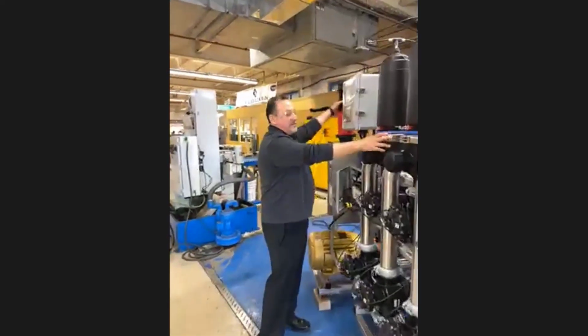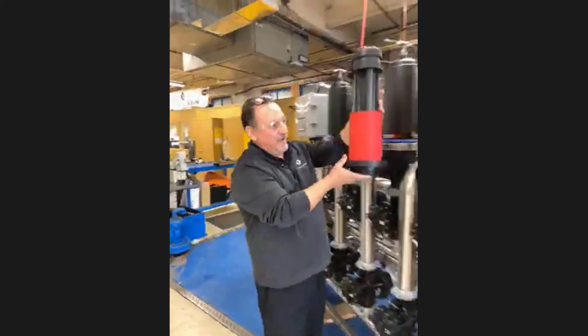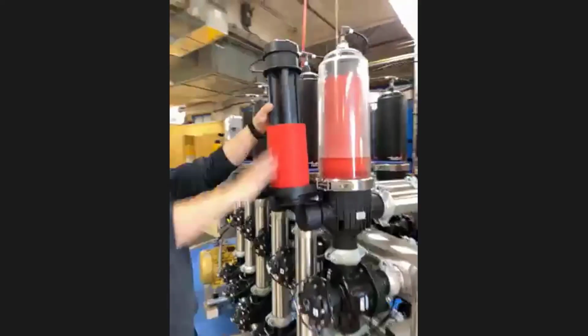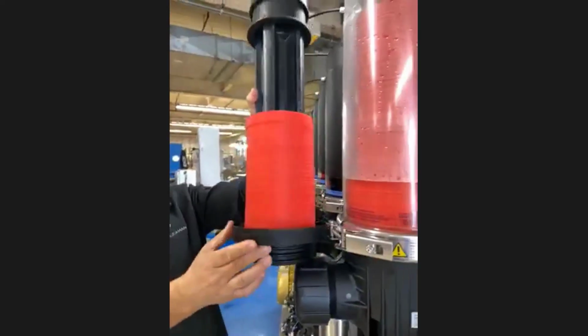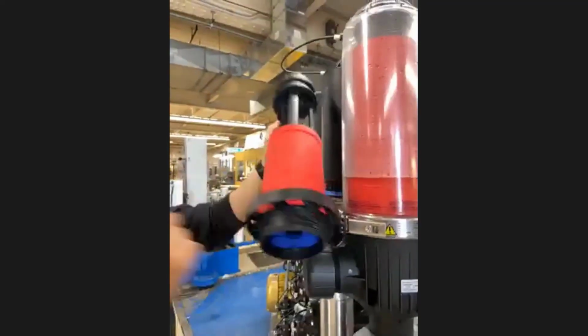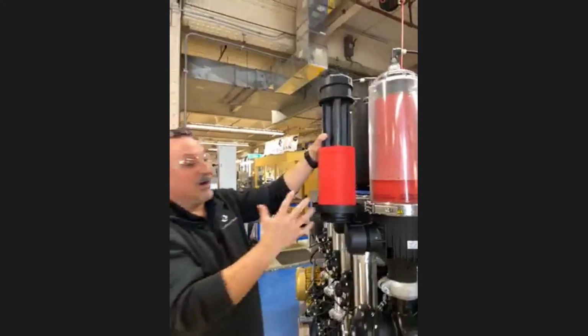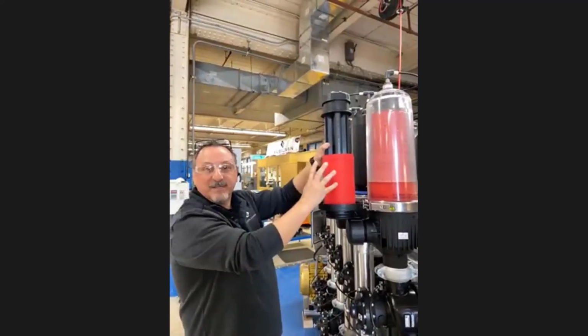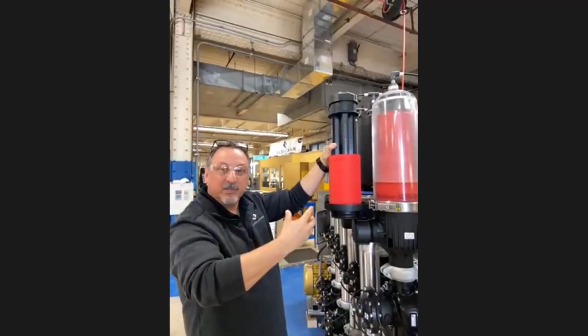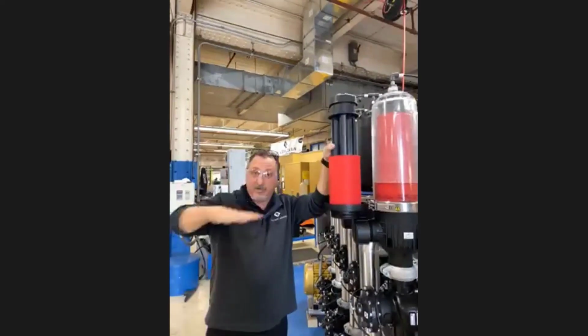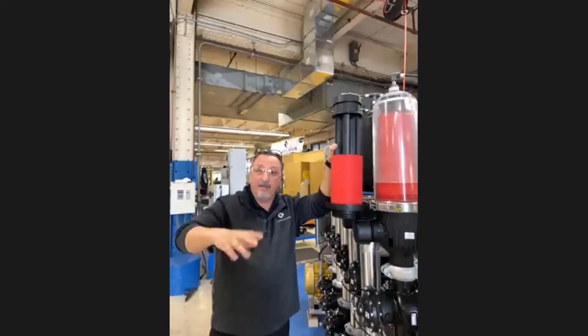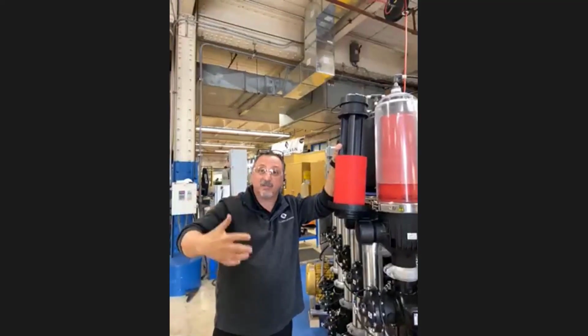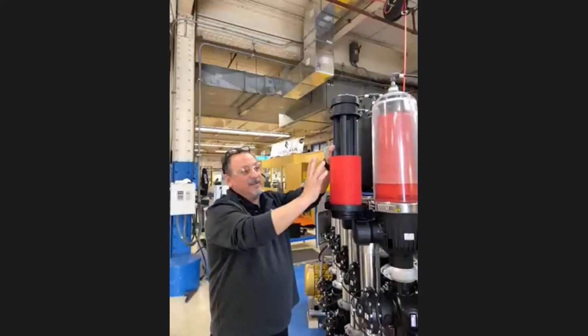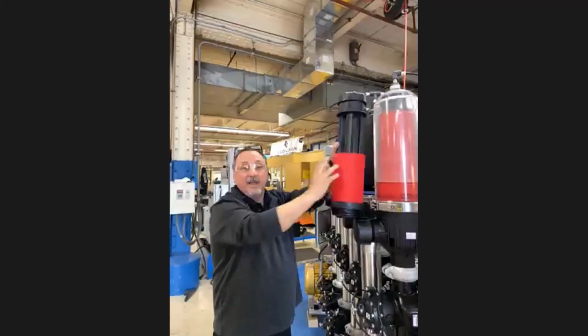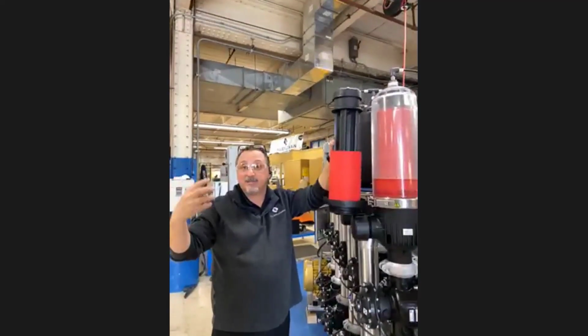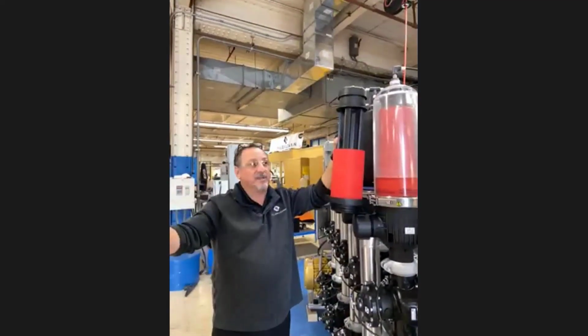When it enters the pod, we have a clear cover to show you how it backflushes, but it's just a stack of discs located right here. It does enter a helix effect at the beginning, which then spins the water. By spinning the water, we can keep a lot of the heavier particles away from the disc stack, prolonging the backflush. We're like in a sand filter, the dirt particles end up sitting on top of the sand, and then creating that pressure differential, then backflushing. I've seen it where we brought in sand and it just keeps it to the outside and it prolongs our backflush, so we don't have to backflush as often as a sand filter or other types of filters out there.